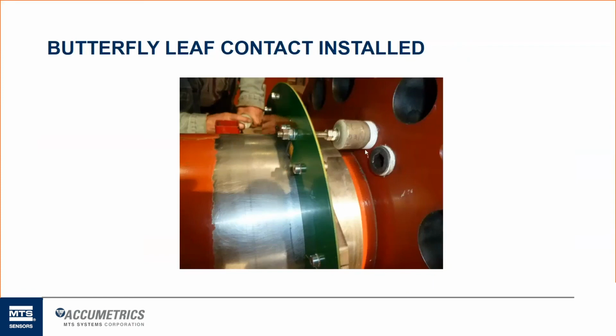We then coat the threads with a special, this looks like Teflon tape. We've since gone to a special epoxy that has PTFE material embedded in it that we use to coat those threads. Then we provide a seal washer on the end of this pipe thread piece to protect against any risk of hydrogen leak that comes out of that bore. We were approached by one of our OEMs many years ago that there was a very, very small chance that hydrogen could leak out, so we've gone the extra steps to prevent any of that. We've actually had this whole assembly tested by a company, and it's able to withstand up to 20 PSI of gas leak pressure, and the spec was only to prevent 10 PSI. So it's more than capable of preventing any risk of leak of hydrogen into the exciter.